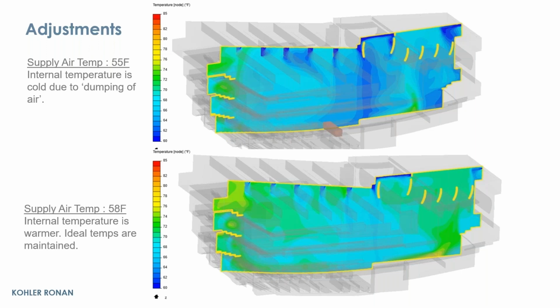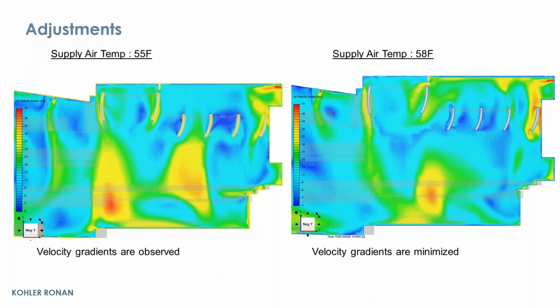Once we did all those tweaks for moving airflow from the front to the back, we saw that the theater was controlled to very good levels. At the stage, which is very important as well, because the Philharmonic wanted, when you have sheet music in front of you, you don't want airflow and things flying away.